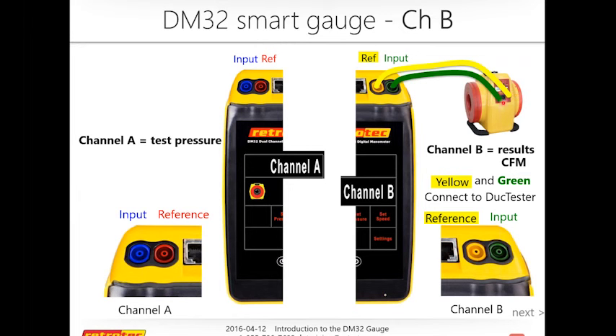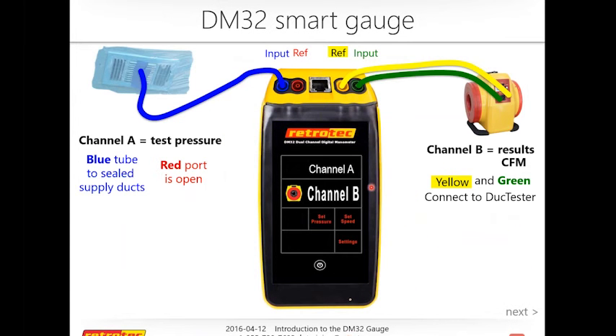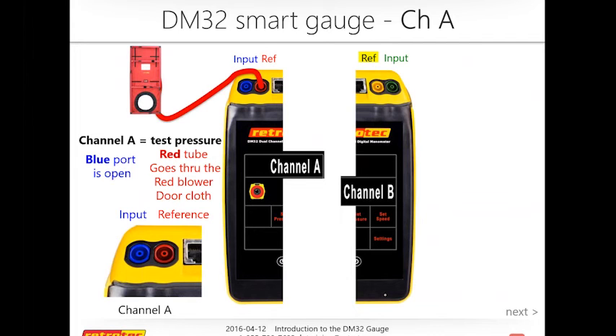So put those together, and here's what you have. You have this tube connected to channel A, and these two tubes connected to channel B, which is going to give us the pressure in the duct tester, and this is going to give us the differential pressure between this area and inside the ductwork. Hopefully that makes sense. And then the same sort of applies to the blower door, though the blower door is a little bit different because here we are actually referencing pressures outside. So you take the red tube and you put it through the red panel, and you put that outside to reference a pressure to the inside, which is usually left open. Unless you have a lot of turbulence in the area, then you can connect a tube to this and put it somewhere inside the building that has less turbulence and give you a nice reading.